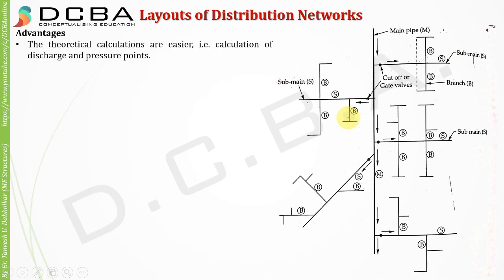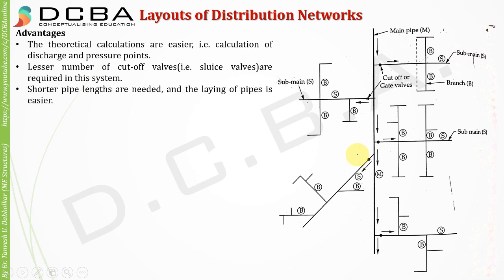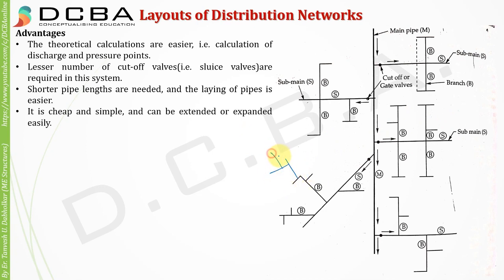Advantages of the dead end system: theoretical calculations are easier — calculating discharge and pressure at various locations is simpler. Fewer cutoff valves are needed; in an entire system with many sub mains and branches, only about five to six cutoff valves are required. Shorter pipelines are needed, laying pipes is easier, it is cheap and simple, and can be extended or expanded easily.